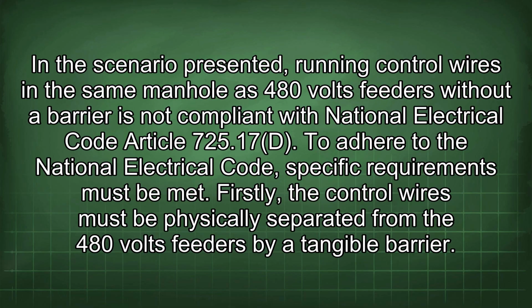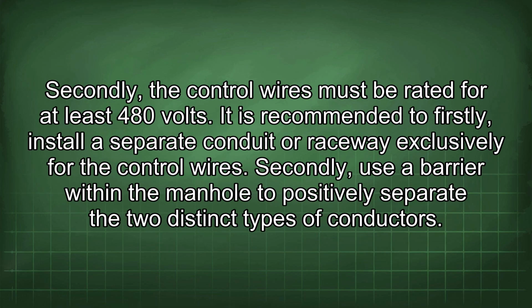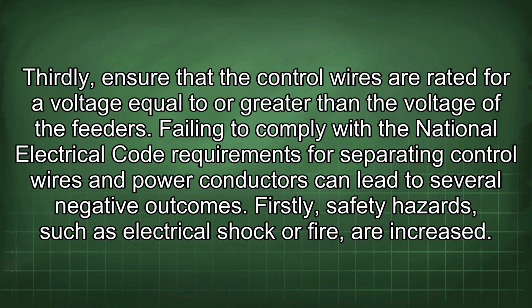Firstly, the control wires must be physically separated from the 480 volts feeders by a tangible barrier. Secondly, the control wires must be rated for at least 480 volts. It is recommended to firstly install a separate conduit or raceway exclusively for the control wires. Secondly, use a barrier within the manhole to positively separate the two distinct types of conductors. Thirdly, ensure that the control wires are rated for a voltage equal to or greater than the voltage of the feeders.